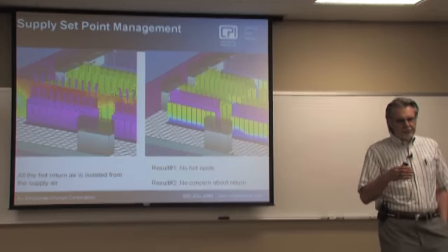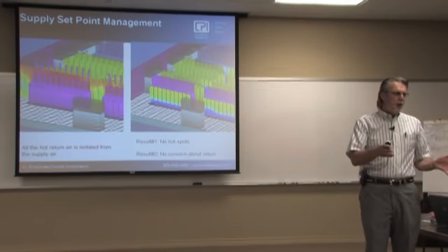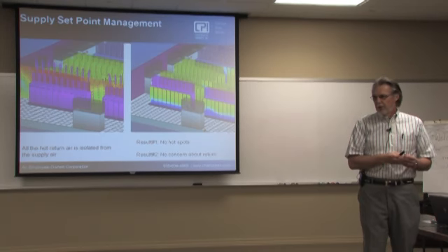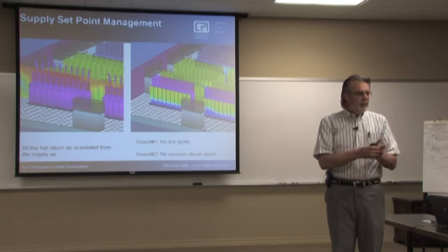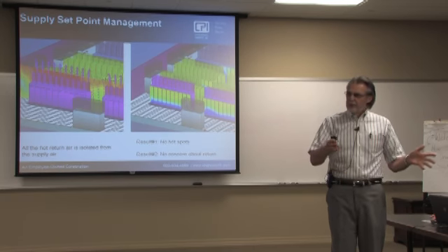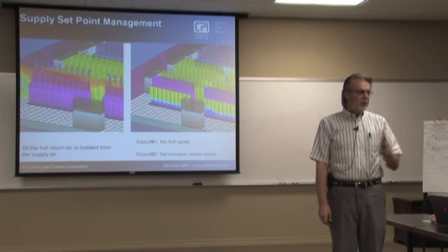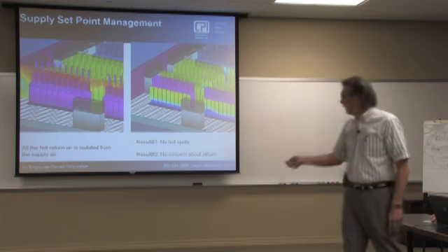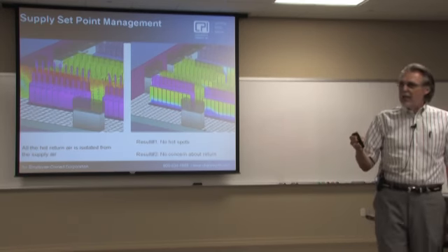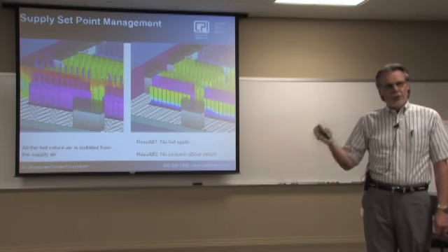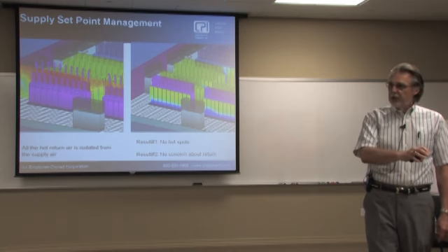This paves the way to our value proposition to the customers. When we completely separate the supply air from the return air, the two most important things that the customer gets: no hot spots, and now he's able to change his thermostat from sticking that on the return air to putting it on the supply air.